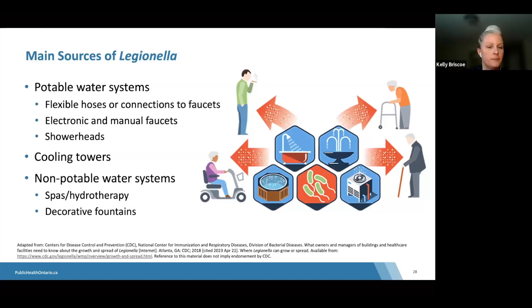So as we've seen, Legionella is prevalent in potable water systems, and there are a number of factors that can contribute to outbreaks in larger water systems, such as systems in hotels or hospitals or long-term care homes. One factor to consider is that they're often complex systems with long sections of potentially small diameter pipes that can provide extensive surface area for biofilm growth. There's also old plumbing that can be a concern as it can experience corrosion or scaling, which can lead to biofilm growth, as well as heat transfer due to uninsulated pipes. This can lead to temperature decreases in hot water, but it can also lead to temperature increases in cold water, which can provide favorable conditions for Legionella.